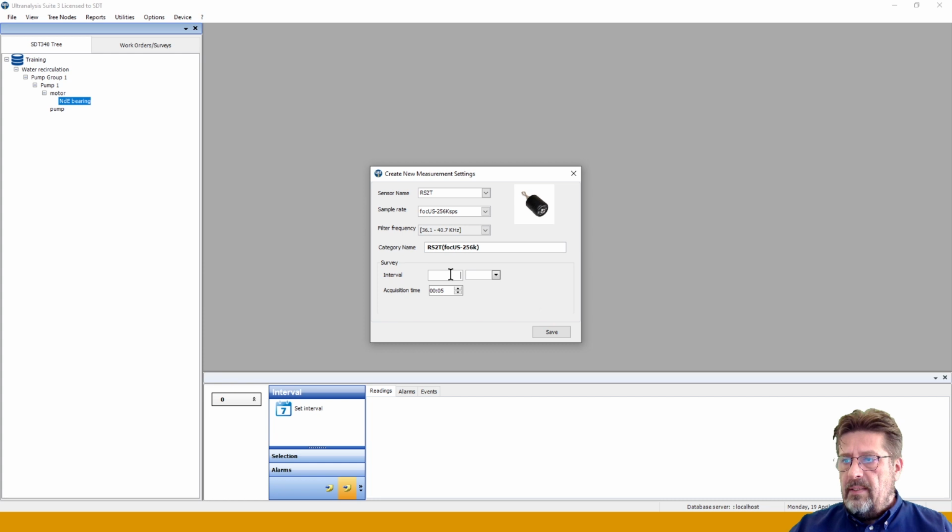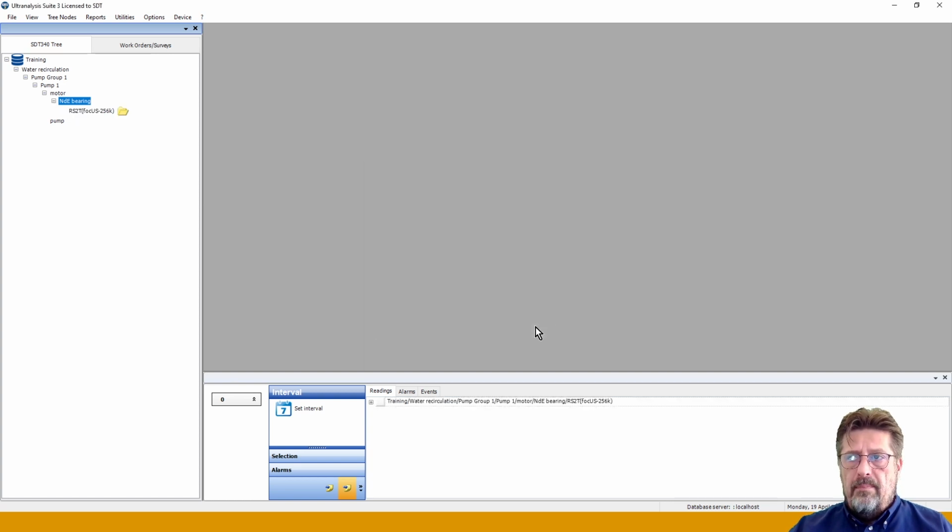Okay, we'll respect that, and we will say that we will do it every month. So you can choose the interval value and the unit. It can be hours, days, weeks, and months. Let's say I want to do it every month. So I defined RS2T, focus 256, every month, duration of the measurement 5 seconds. Save. Fine.